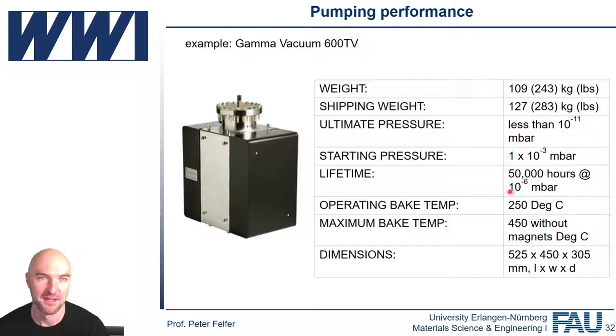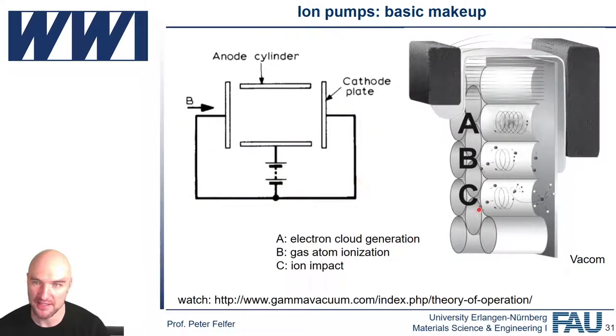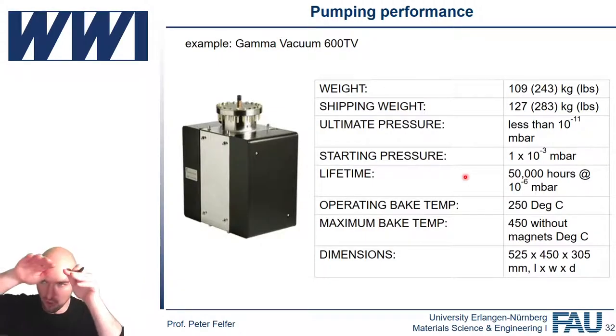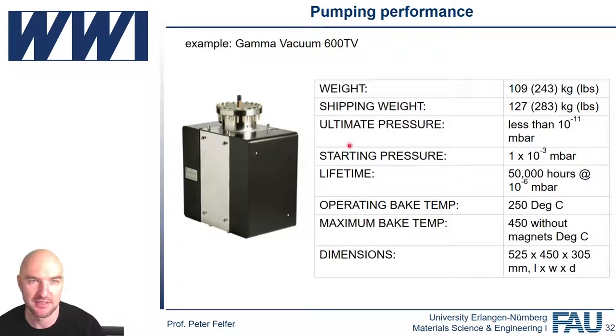The problem with that is, though, that the ions that you create can escape your pump. And if you have an atom probe, they can get sucked into your detector. So in the LEAP systems, you always have shielding around the detector in the entire flight path, just simply so that the ions from the pump don't get sucked into your detector. If you don't have to deal with it, it's good if you don't. But apart from that, they're extremely robust.